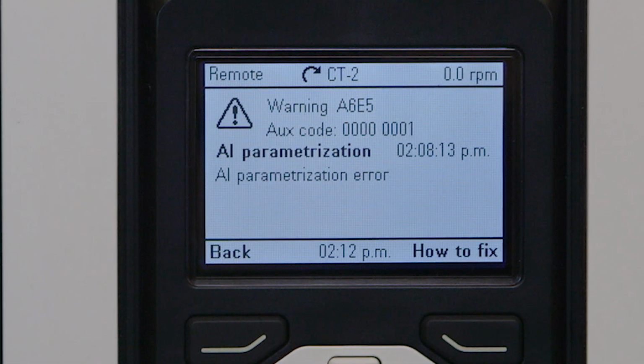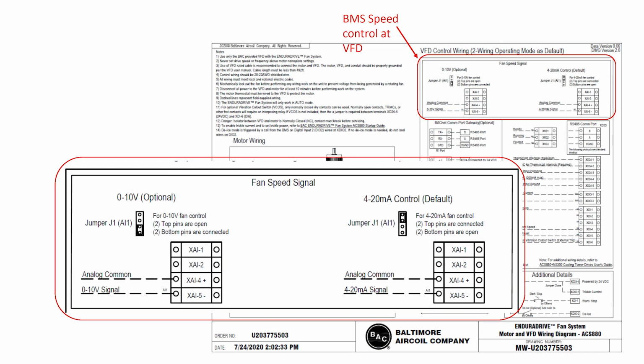The AI parameterization error occurs when your dip switch jumpers J1 and J2 do not match the programming in the VFD for AI1 and AI2 settings. This error warns you that the jumper J1 and the parameter 12.15 currently do not match each other, or that jumper J2 and parameter 12.25 do not match each other.